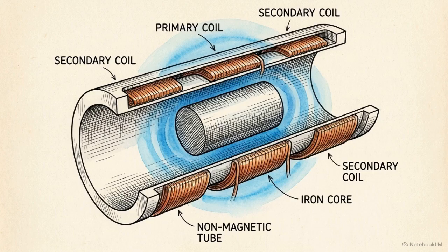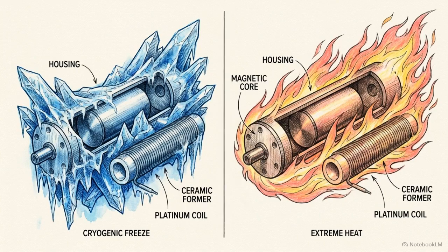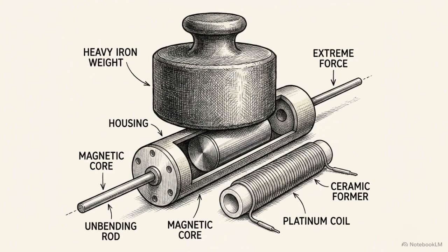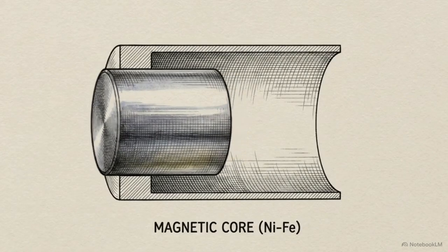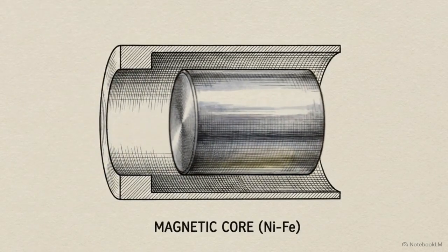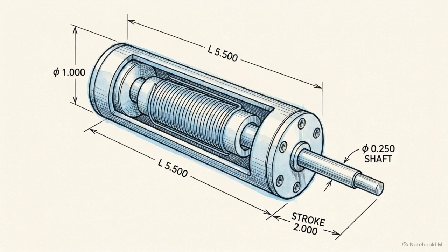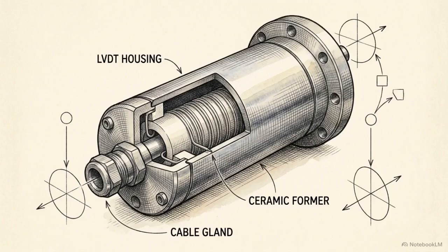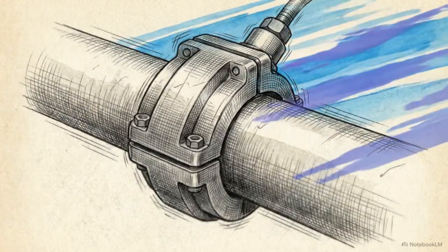Because the core floats magnetically inside the cylinder without making physical contact, there is zero friction, giving the LVDT an almost infinite service life. It is physically robust under extreme conditions, operating reliably from -265 degrees Celsius up to 600 degrees without permanent damage, even if mechanically pushed past its design limits. Its response time is virtually instantaneous, strictly limited only by the physical inertia of the iron core itself. The LVDT is an elegant piece of engineering. It integrates the sensing movement of the core and the conditioning unit of the opposing secondary coils into a single mechanical housing. Despite robust designs, transducers are incredibly precise instruments.